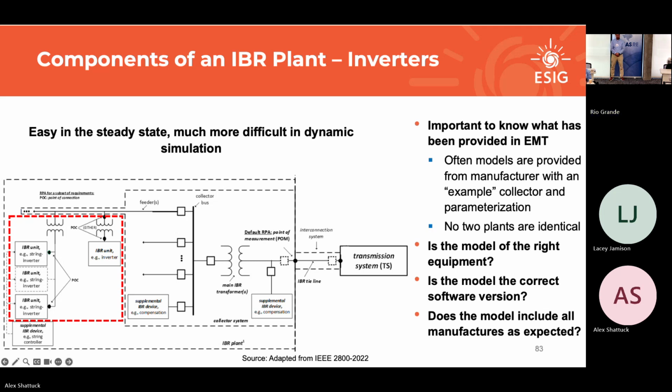But one thing that helps is that there are no two identical IBR plants. That's a hard statement, but there probably will never be two exactly the same parameterized models. There are site-specific tunings, collector systems are different sizes, and there are different numbers of inverters. So if you get two models side by side from the same manufacturer and they're identical, they're probably both example models, or someone copy pasted, and they're still not a plant model. This is something you don't really have to talk about in the PSPD world, but it is confusing and misleading in the EMT world.